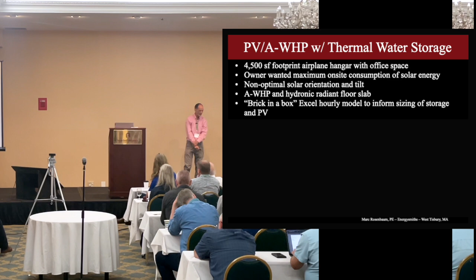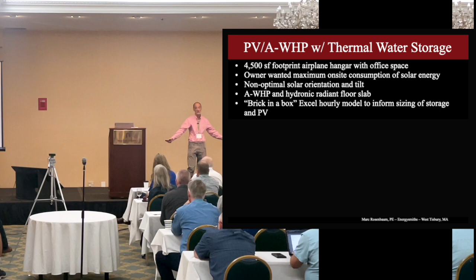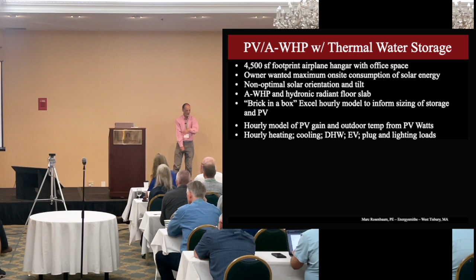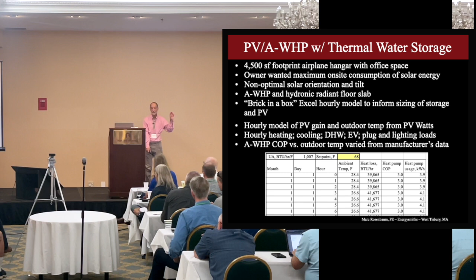I did a brick-in-a-box Excel model to inform the sizing of the storage, because I want to use the air-to-water heat pump to store some of that energy in water, since I'm already working with water. I've got a hydronic radiant slab, an hourly model of the gain from the PVs, and an hourly model of the load of the building. It's more complicated—I've got all these other loads built into this model. I built an Excel spreadsheet with 8760 hours, and I've got the heat pump COP off the manufacturer's data based on outdoor ambient temperature, so that's varied as well.